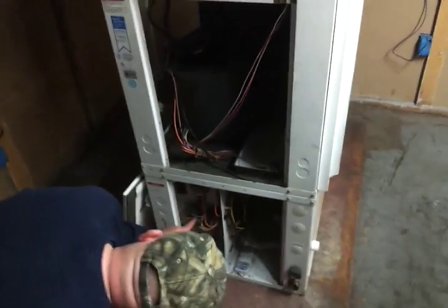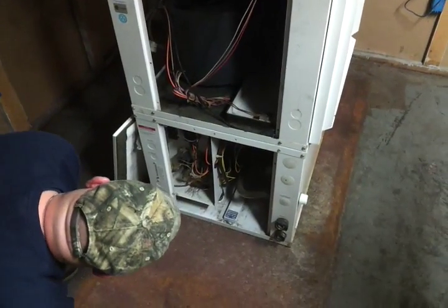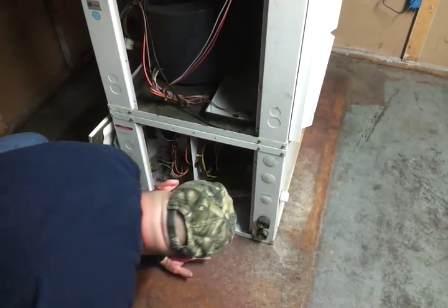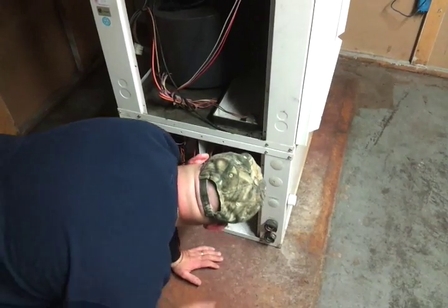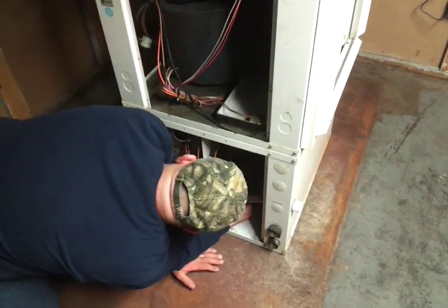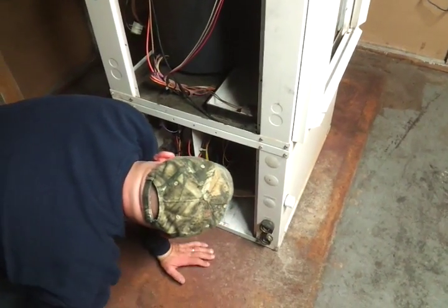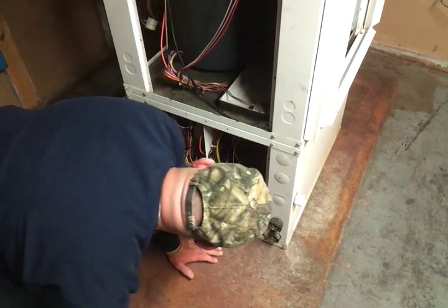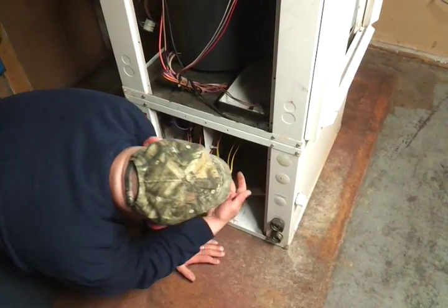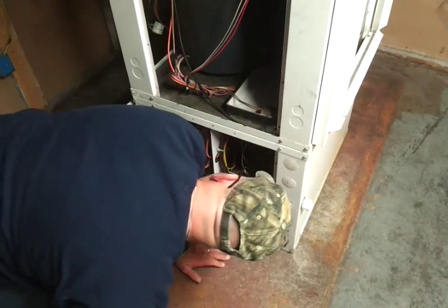No, it's got that standard WaterFurnace board. They've cut the freeze sensor right here, there's 2 yellow wires, and they pulled the sensor off of the refrigeration line and wire-nutted it together.